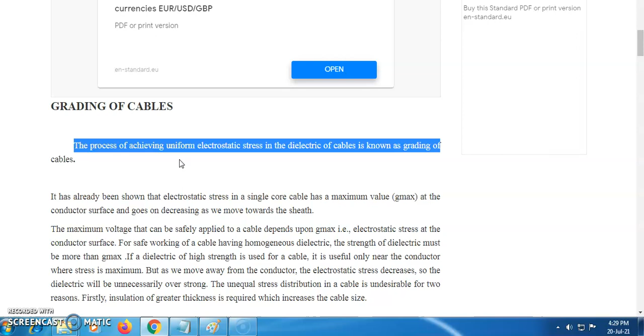With respect to cables, another important thing is grading of cables. The process of achieving uniform electrostatic stress in the dielectric of cables is known as grading. The potential stress is maximum near the conductor and minimum elsewhere, so to make the electrostatic stress uniform, we need to go for the process called grading. That is very important. So grading is the process of achieving uniform electrostatic stress in the dielectric of the cables.